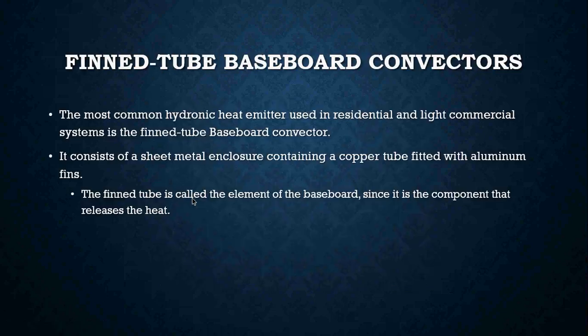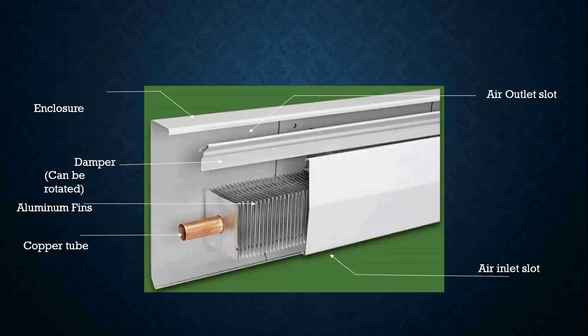The most common hydronic heat emitter used in residential and light commercial systems is the fin-tube baseboard convector. It consists of a sheet metal enclosure containing a copper tube with aluminum fins. The fin-tube is called the element of the baseboard, since it is the component that actually releases the heat. Your hot water runs through the copper tube all the way along and back to the boiler — a constant heating loop — and as that hot water passes through the copper, the heat is transferred to the aluminum fins.